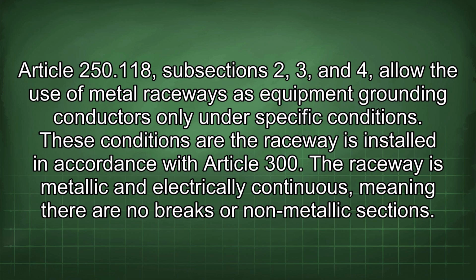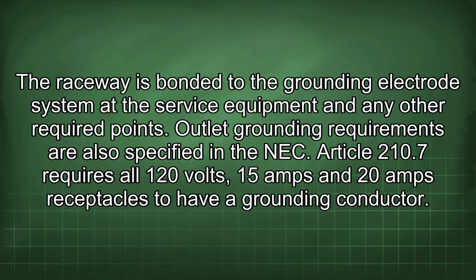These conditions are: the raceway is installed in accordance with Article 300. The raceway is metallic and electrically continuous, meaning there are no breaks or non-metallic sections. The raceway is bonded to the grounding electrode system at the service equipment and any other required points. Outlet grounding requirements are also specified in the NEC. Article 210.7 requires all 120 volt, 15 amp and 20 amp receptacles to have a grounding conductor.